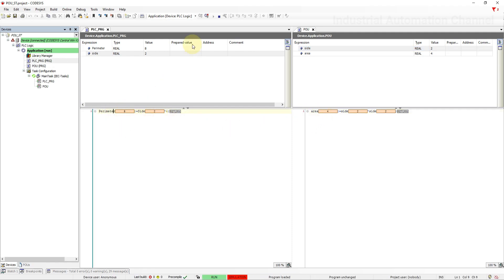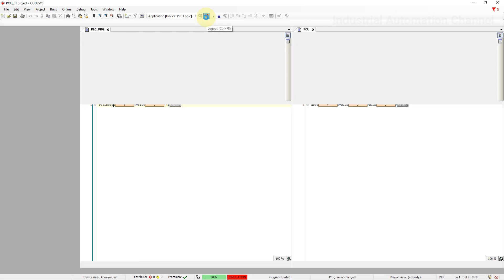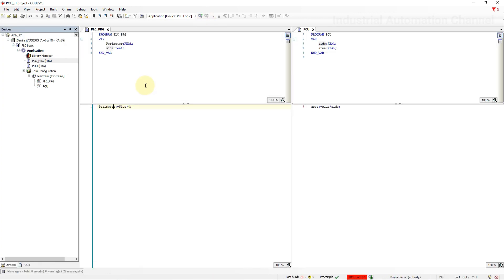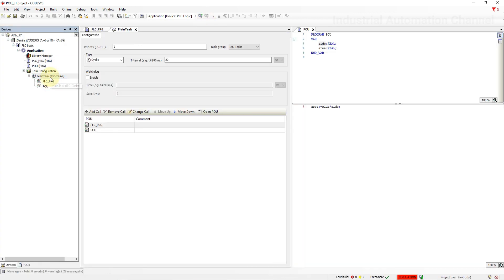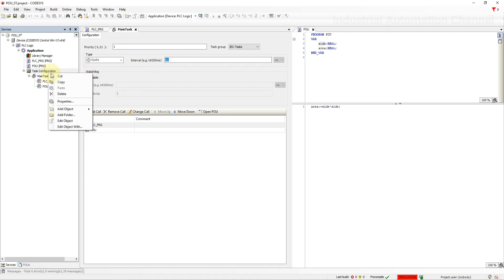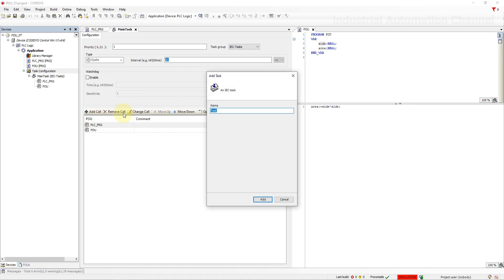We can also add a new task if we want. Right now we have just a task that is executing every 20 milliseconds which is our main task. Let's say we want a new program to be executed every thousand milliseconds. So we need to create another task. To add a new task click on task configuration, add object and add a new task.